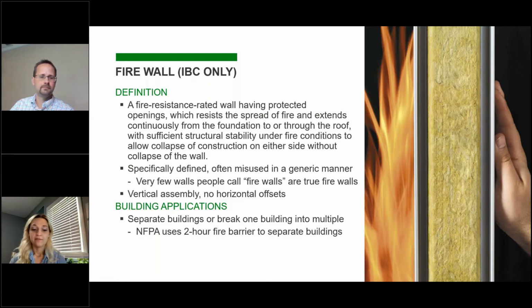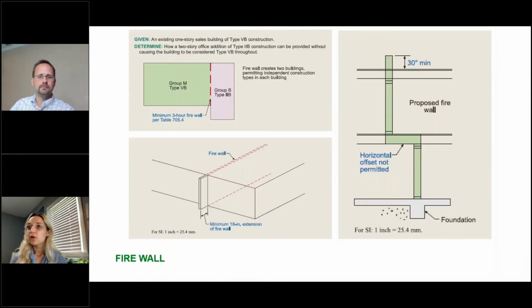This wall is going to go from foundation up to the roof slab, completely straight up. It won't be on a single floor. It's going to chop through the whole building. Exactly. So we may use this to get more out of height and area restrictions for buildings, to allow a larger footprint, or to separate construction types. It's important that we acknowledge that in most cases, the two things on the sides of the firewall are actually going to be different addresses. So by calling something a firewall that's not, we end up requiring a lot more architectural and mechanical systems coordinated through it. So it's pretty rare, unless you're separating a building, to see the term firewall. And for what it's worth, NFPA 101, if it is identifying a separation between buildings, will use a 2-hour fire barrier rather than firewall.